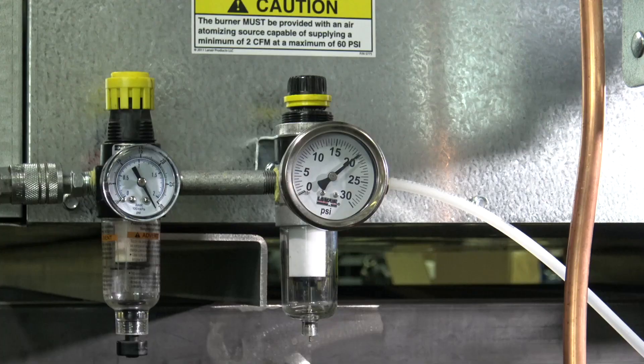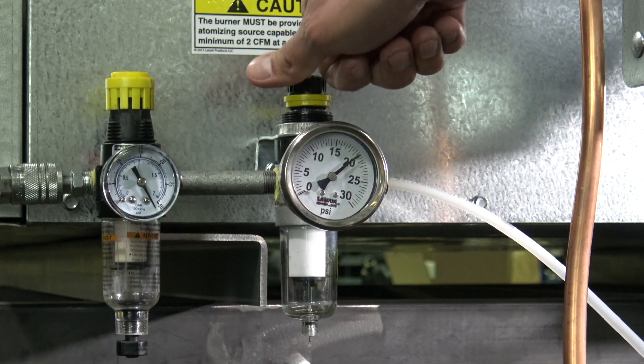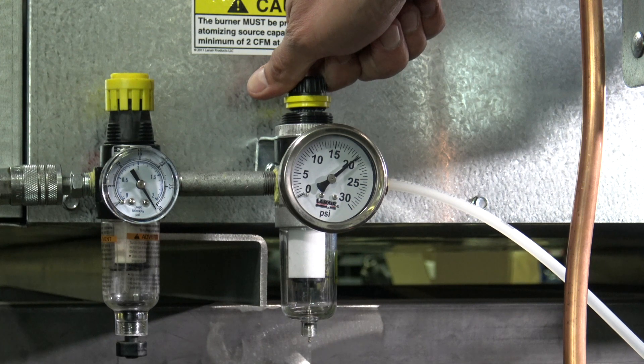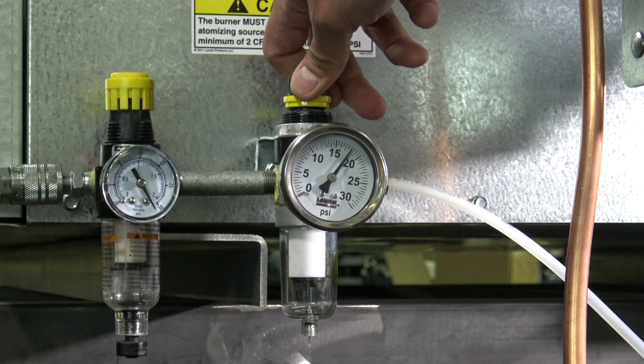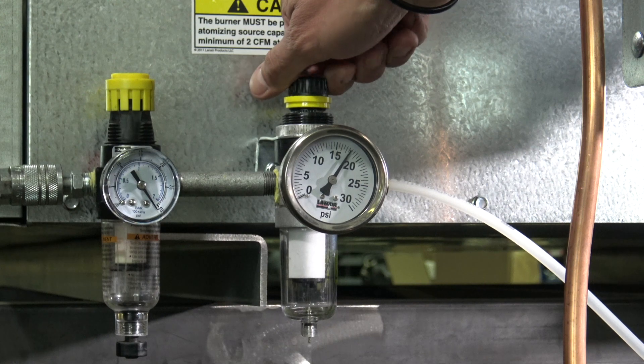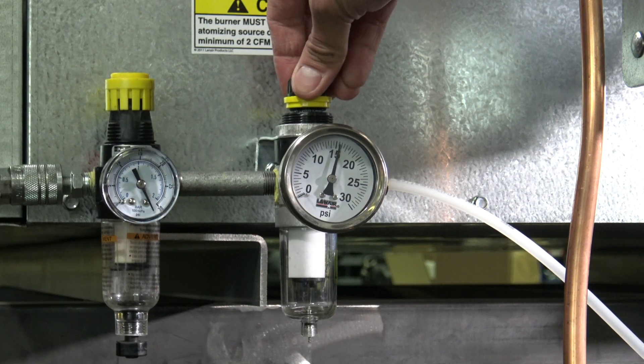For a unit that is under-firing, we will reverse our approach. Begin by reducing the atomizing air pressure at the secondary air pressure regulator in 1 psi increments until the flame is correct, or down to 1 psi below the recommended air pressure setting range for the model, whichever comes first.